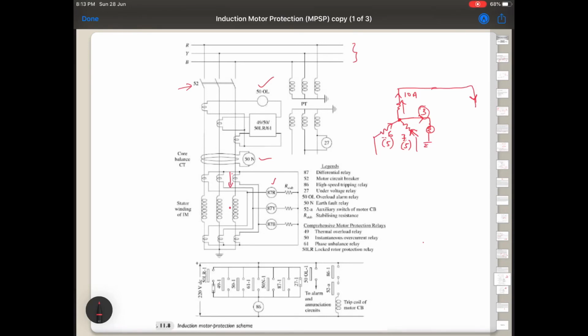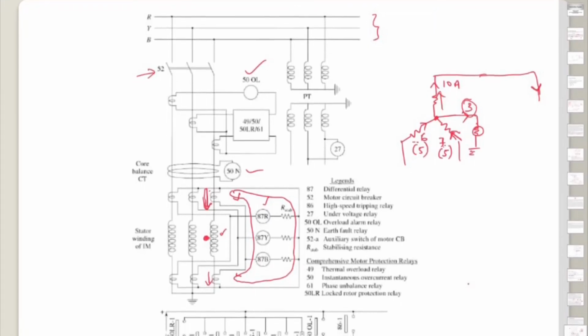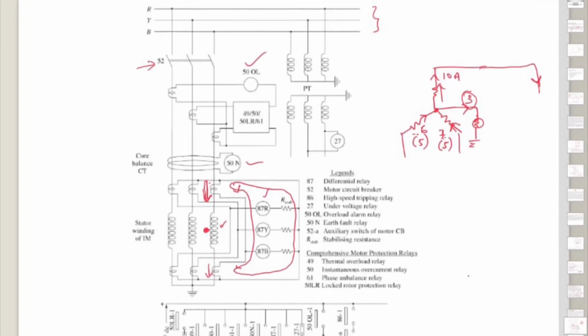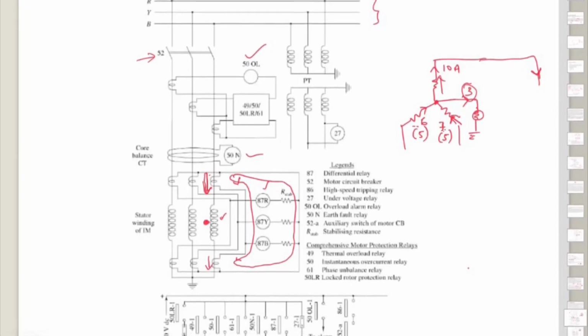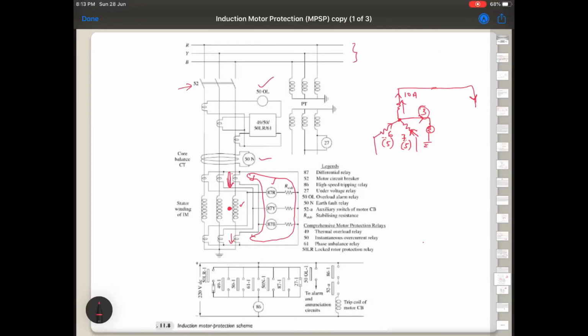If this high current is entering, the sudden change of current will not be allowed by the inductor. Therefore, during normal condition the current would have been like this. The incoming current is equal to outgoing current during normal operation, but there is a fault here. Since there is a fault here, the current sensed on the input side and the output side is different. Sorry, I referred to it as a relay. Actually it is the primary of the CT and the secondary of the CT on either side of the rotor winding or the stator winding. Since the current is different, the difference current will flow through the relay. That relay will operate based on the difference, hence it is called a differential relay.